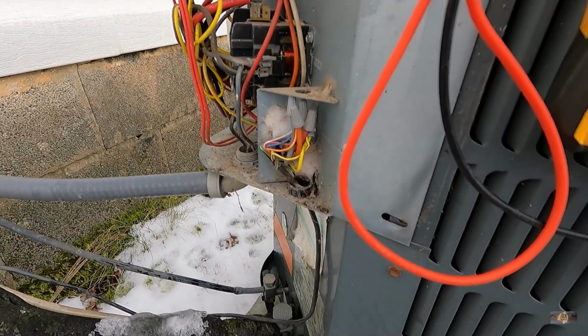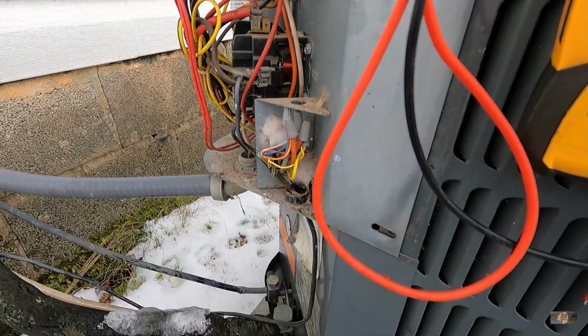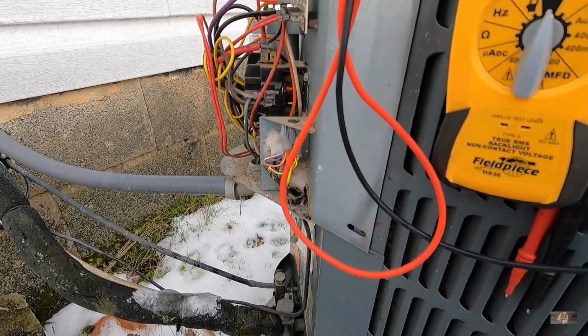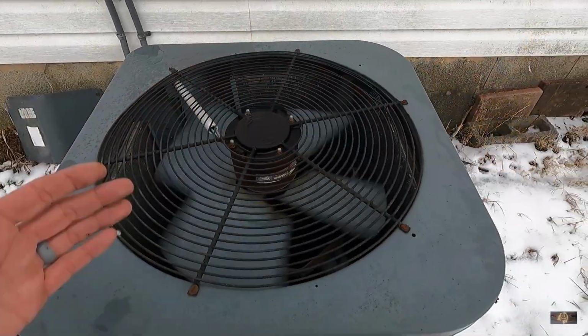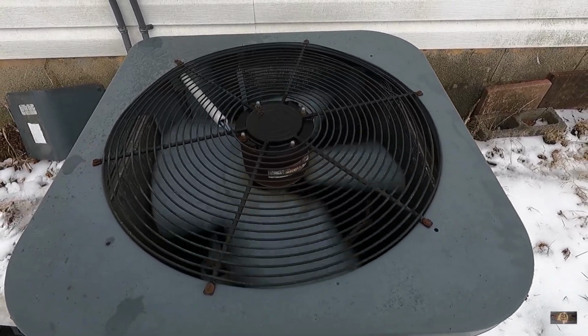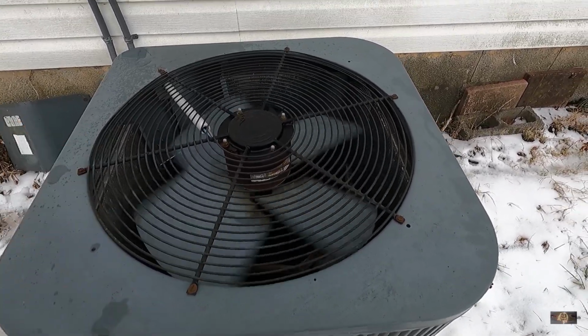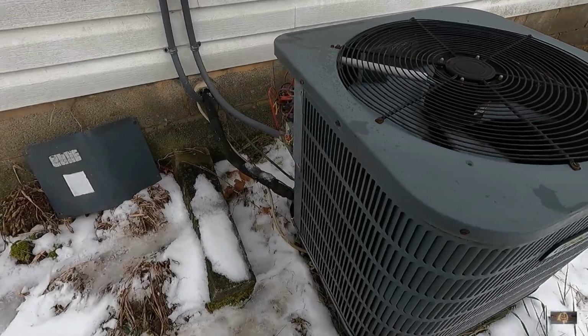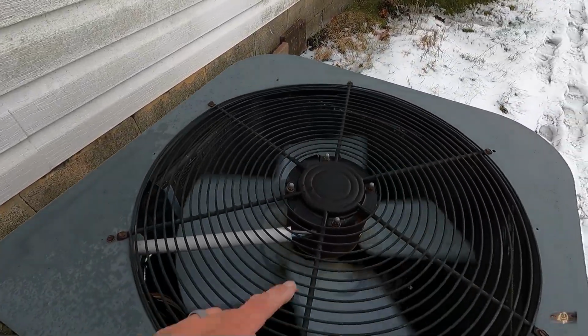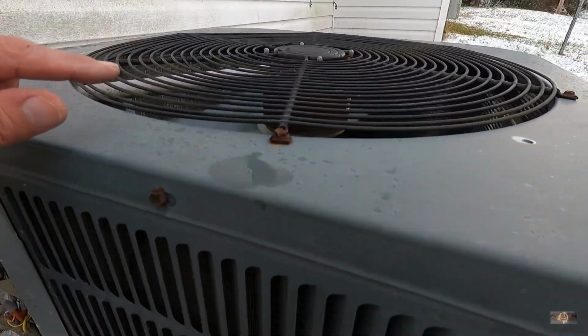I'm gonna put an amp clamp on the compressor and see if I got amps drawn through it. I might have to grab my probes too. We're just gonna see. Didn't pull a lot of amps on the inrush. Only 13. It is, the compressor is running. They said what's going on is you can hear this little clicking noise in there. You hear that?